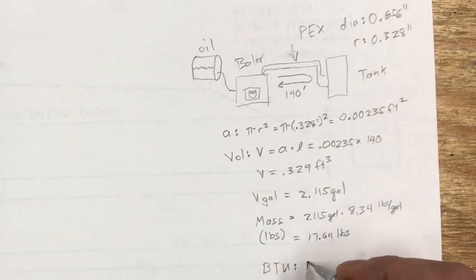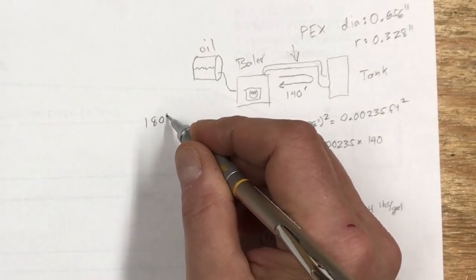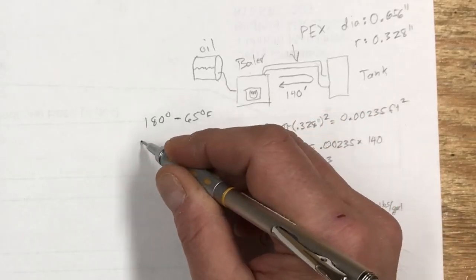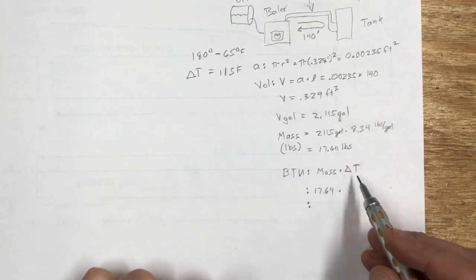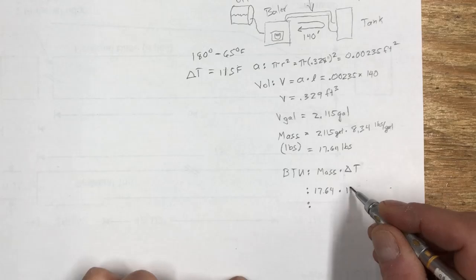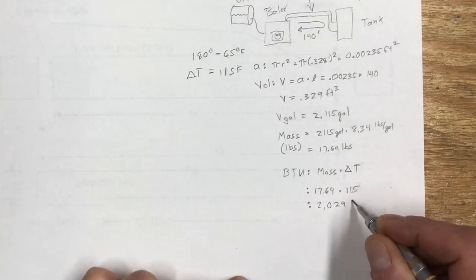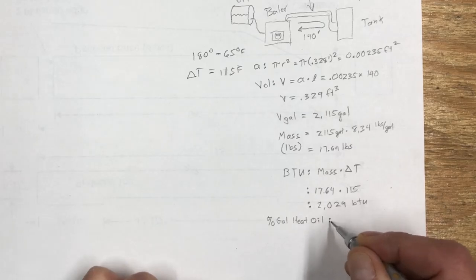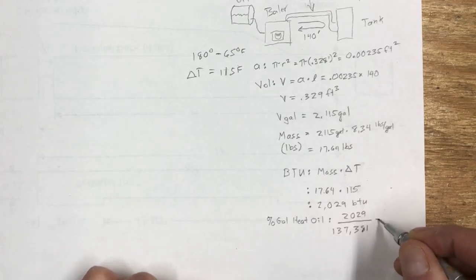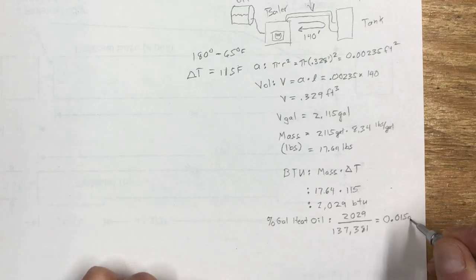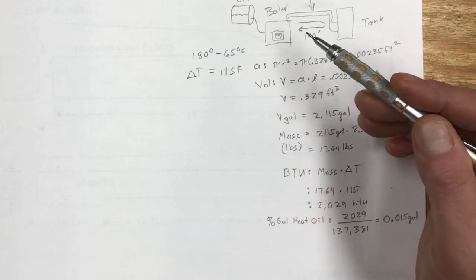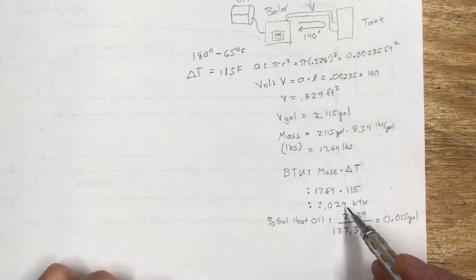And the BTU is the mass times the delta T. My boiler heats the water up to 180 degrees and I'm assuming that it's coming down to an ambient temperature of around 65 degrees and this is all fahrenheit. 115 degrees. If you come down here to calculate the BTU it's the mass times the delta T, so 17.64 times 115 and that turns out to be about 2029 BTU. Now a gallon of home heating oil I discussed in another video is 137,381 BTU in a gallon. So the percentage of a gallon heating oil is 2029 divided by 137,381 and that equals 0.015 gallons. So the amount of heat if this is 180 degrees that sits in these pipes and eventually cools off to 65 degrees is about 0.015 gallons or 2029 BTU.